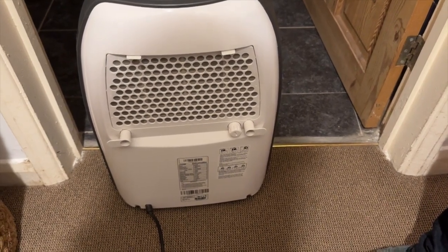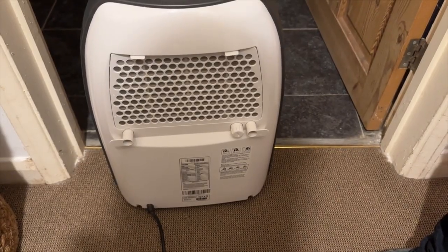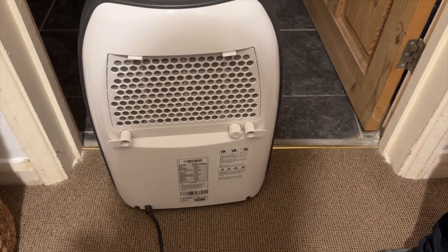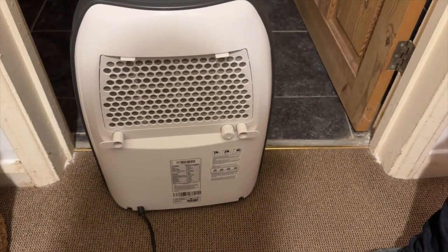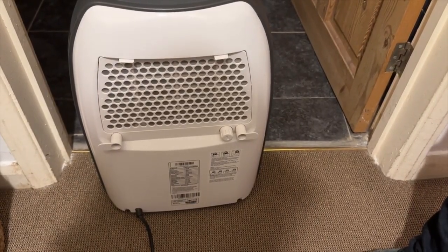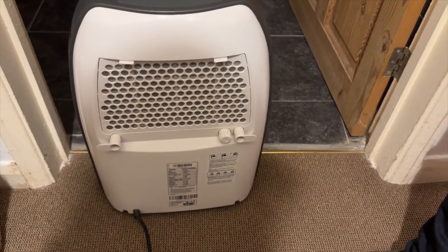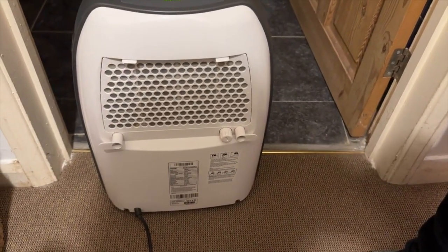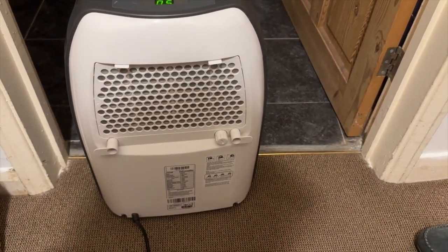And even if the place was constantly ventilated, if you don't have any heating, you'll end up having the outside humidity coming in, and when it's raining, it's 100% relative humidity. So you'll be drawing that vapour in from the outside, and if you're not removing it or you're not heating the air, you'll end up having condensation and mould.